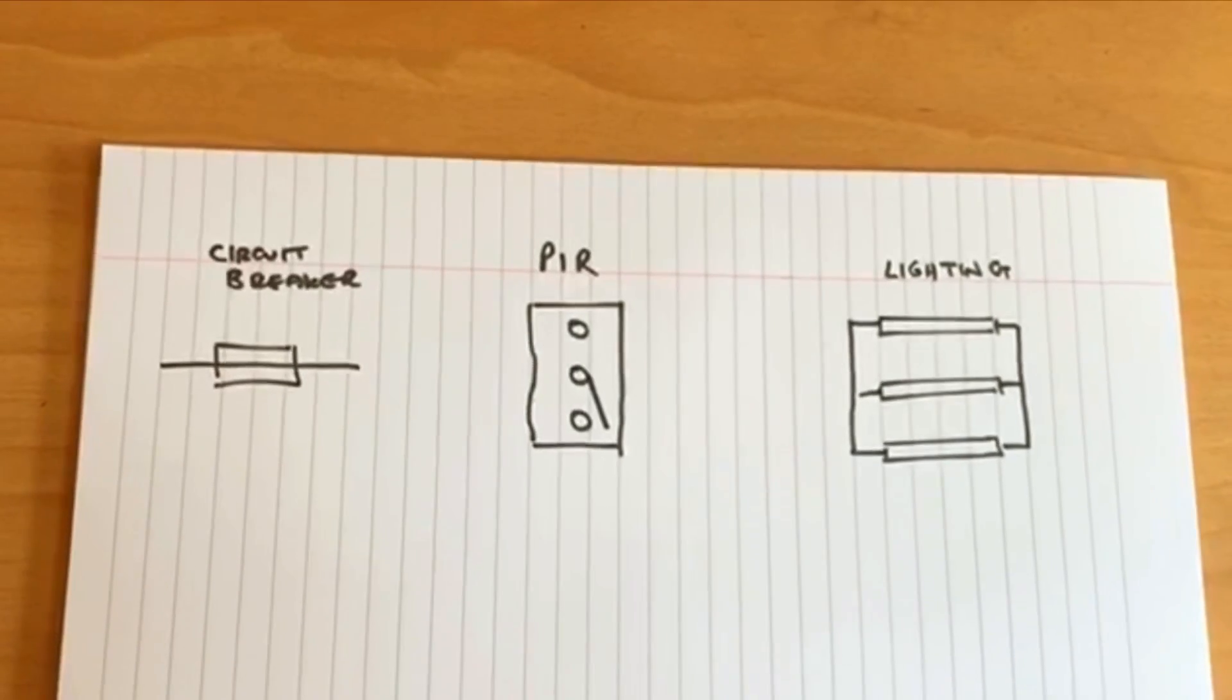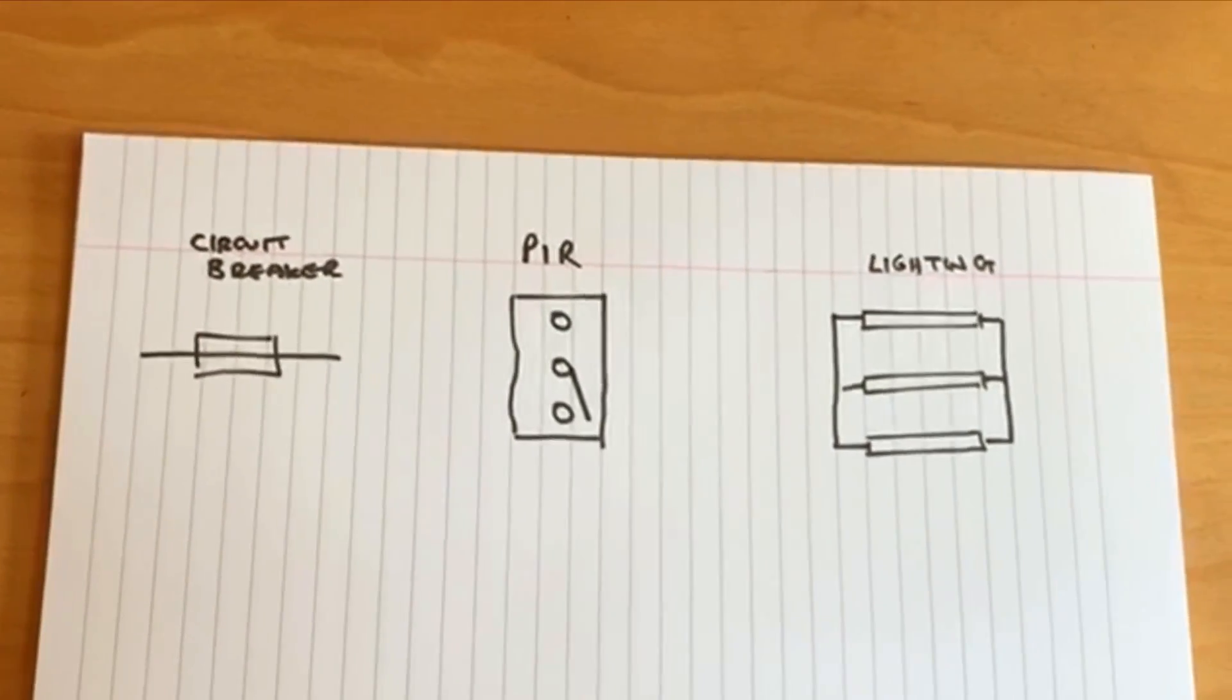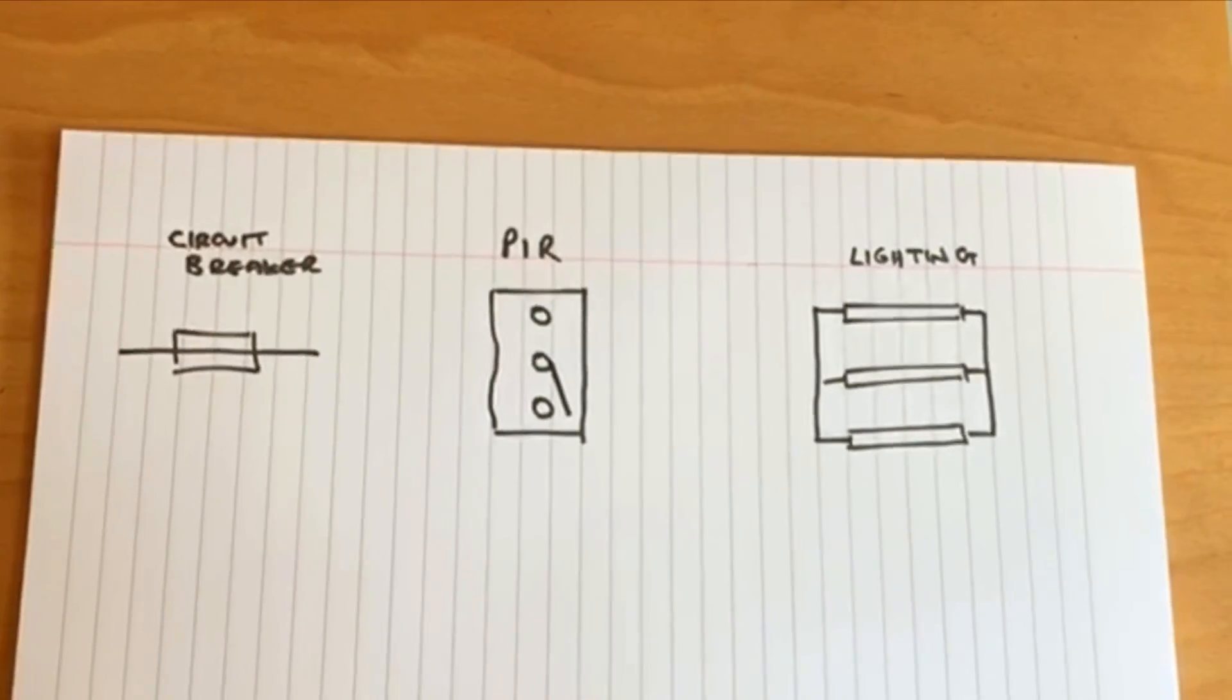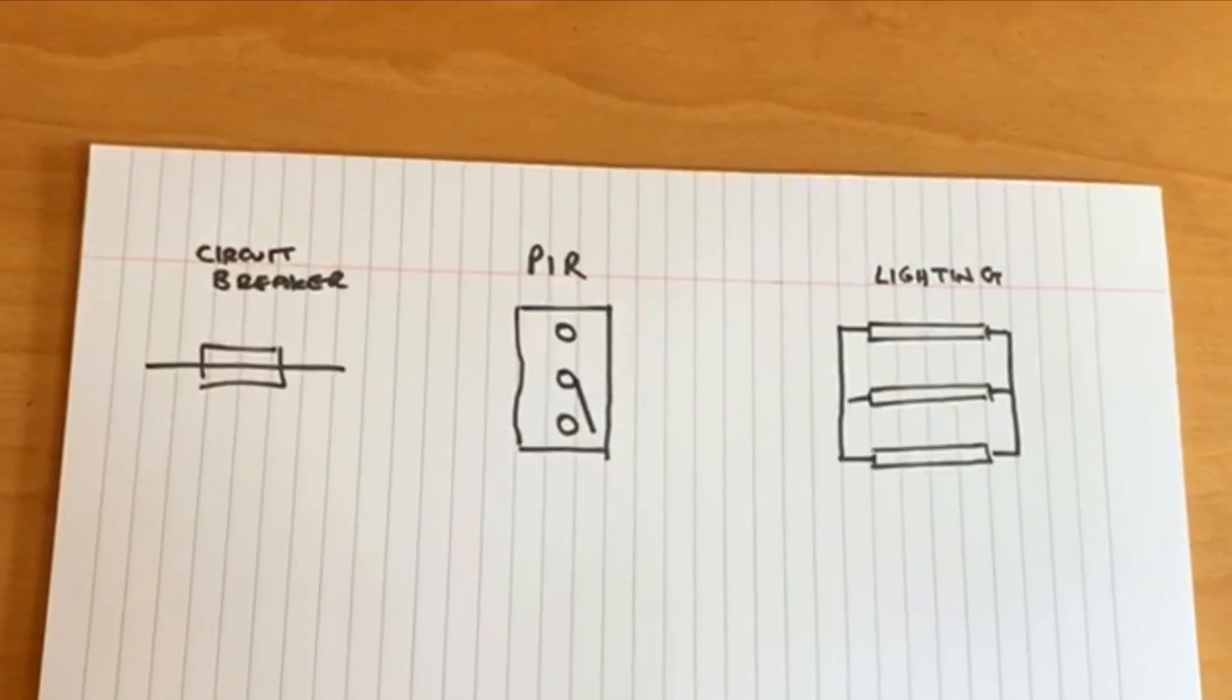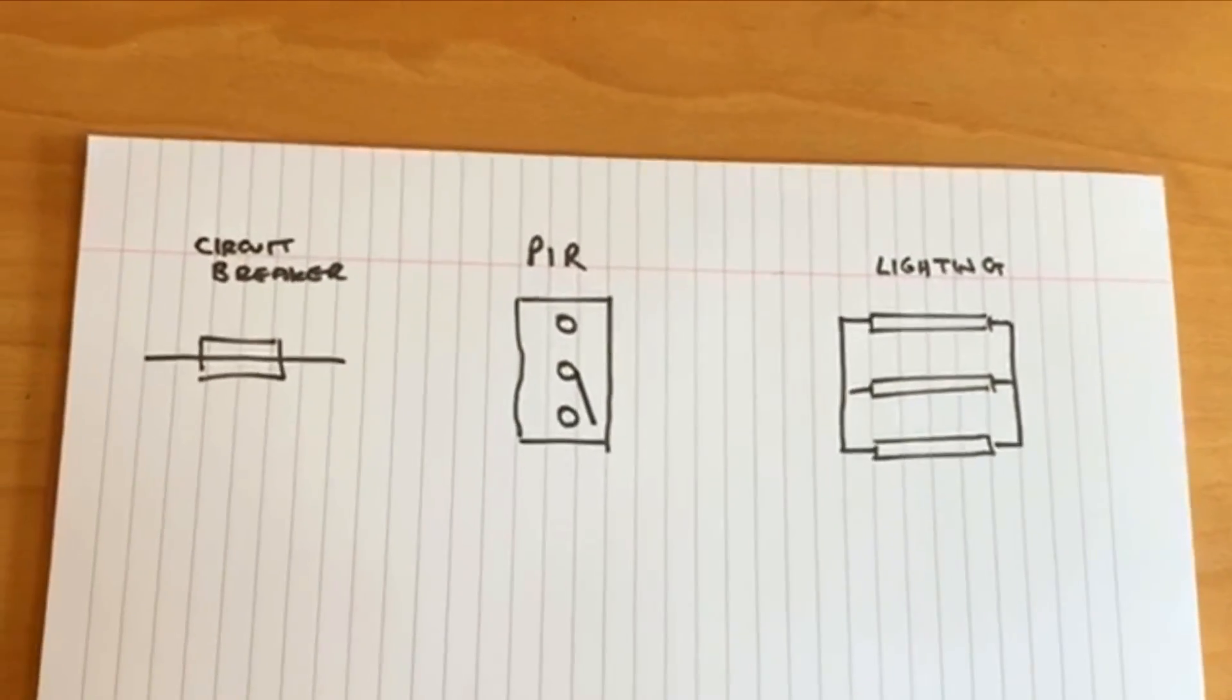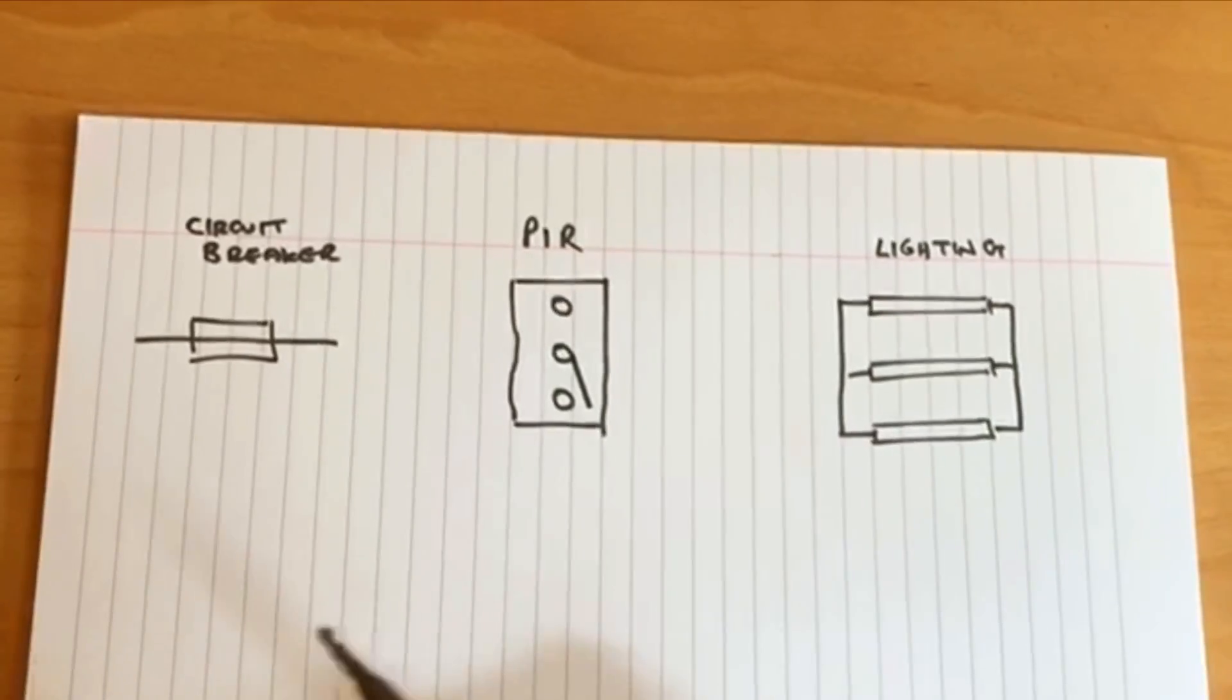The first thing to think about with a PIR: generally there's four connections. There's usually a supply live connection, a switch live connection, and then there's usually two neutral connections, but both of those neutral connections are linked together so I'm just going to draw it as one here.